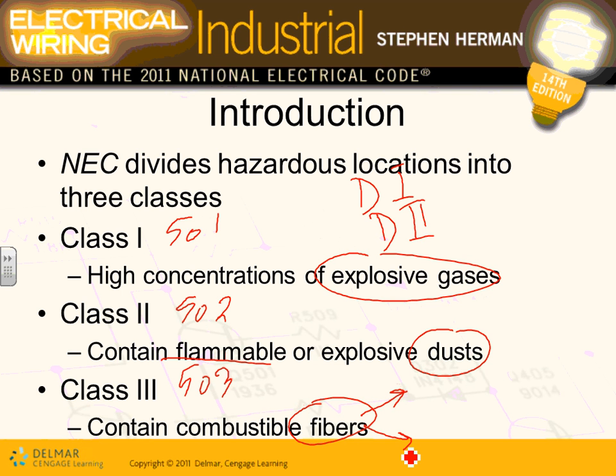What's Div 1? Div 1, the hazard exists at all times, inside the tank that has gas. Around the tank that has gas is Div 2, because there's no gas around the tank unless you have a spill. Any comments, guys, about Class 1, Div 1, and Div 2? Class 1, Class 2, Class 3, Div 1, Div 2. All of them have divs. So there's a Div 1 here and a Div 2 here, and also a Div 1 here and a Div 2 here. All of them have Div 1, Div 2. Div 1, the most hazard; Div 2, the least hazard of that particular hazard.